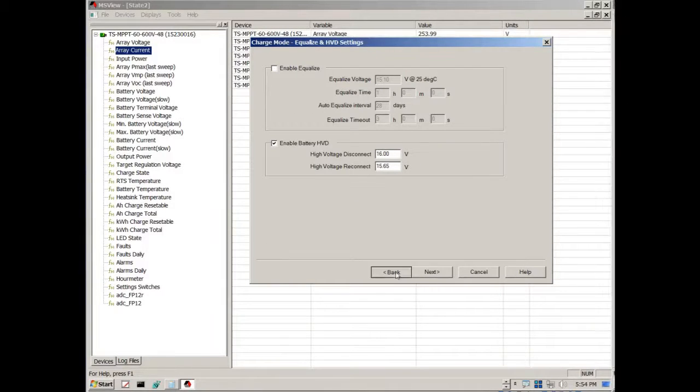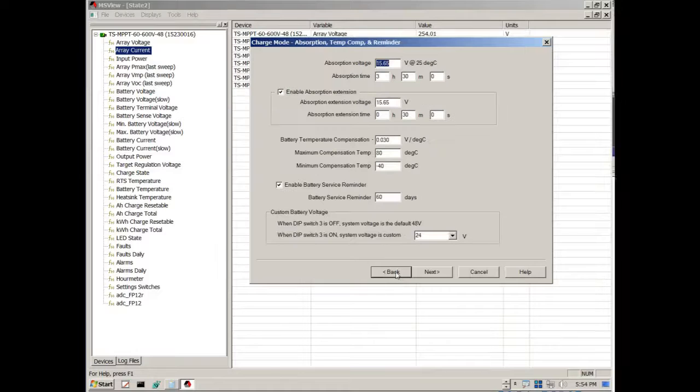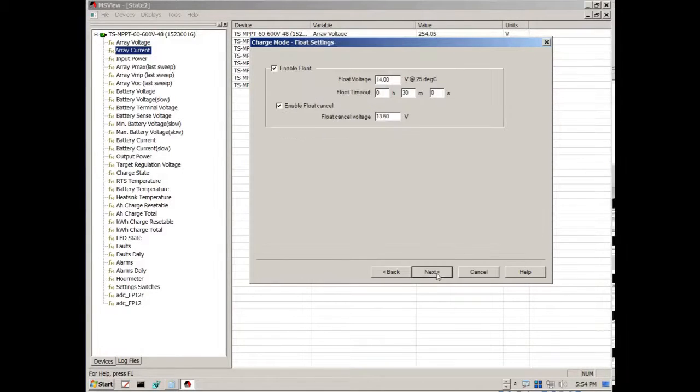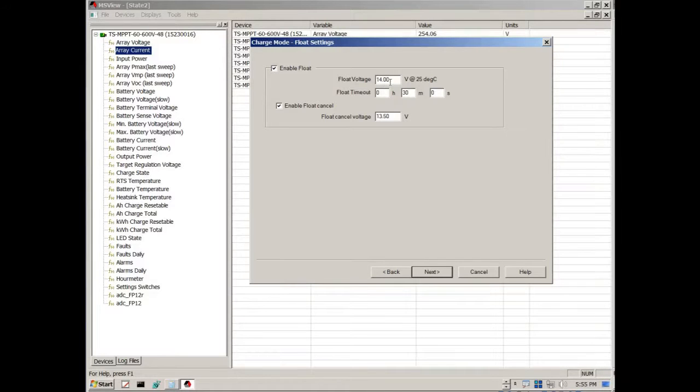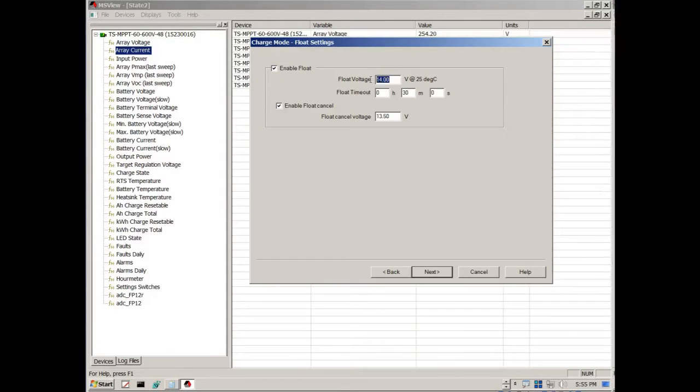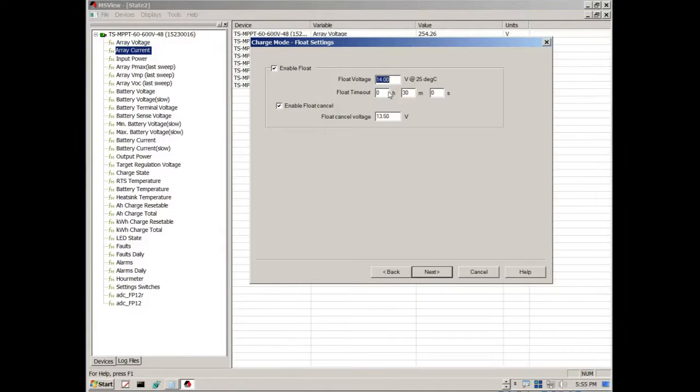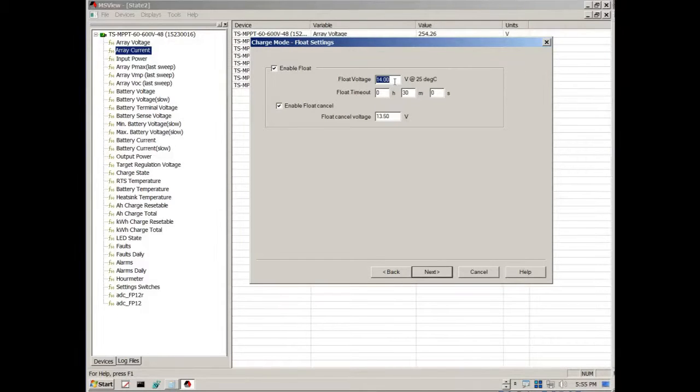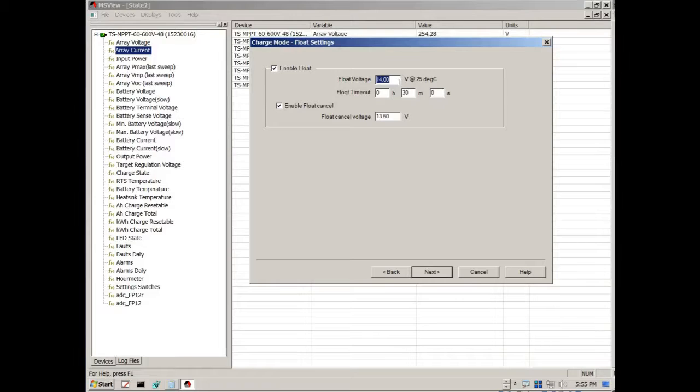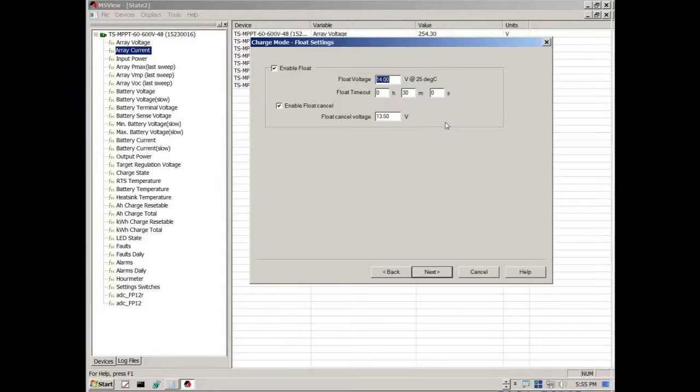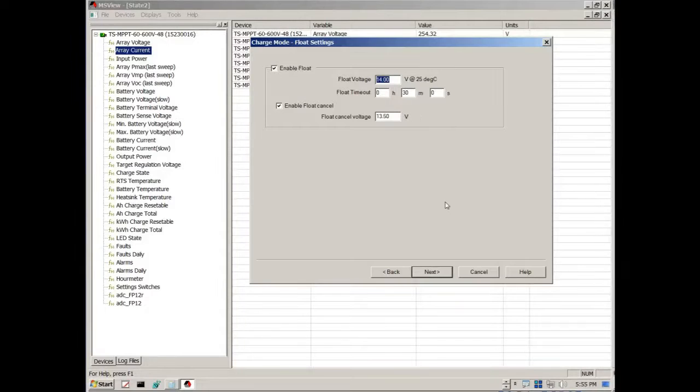Programming it can be a little tricky. For instance if you come here and say the float voltage, you're tempted if you've got a 24 volt system to put 28. However the way it's programmed, you have to program it as a multiple of two. So for instance this is 14 volts, and this is typically for a 12 volt system. So what I have to do is say okay 14 times two, that will equal my float voltage, which would be 28.